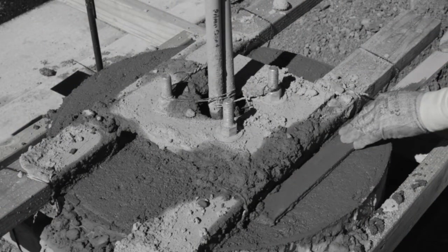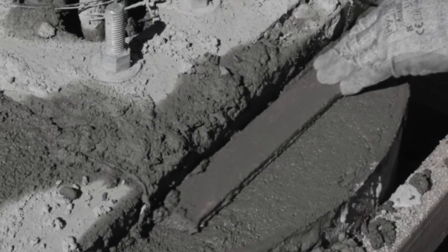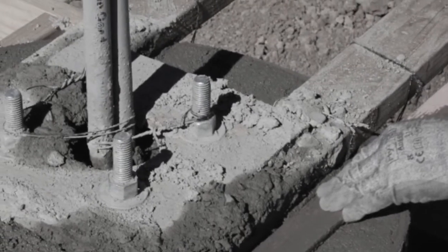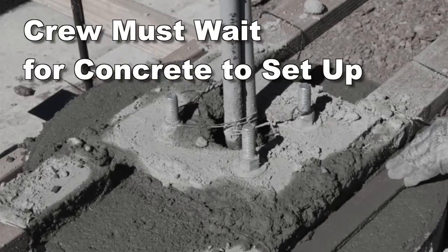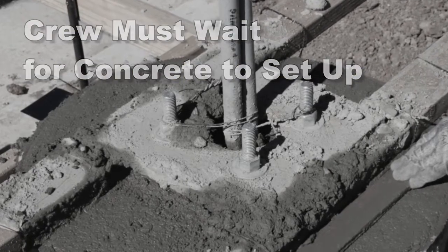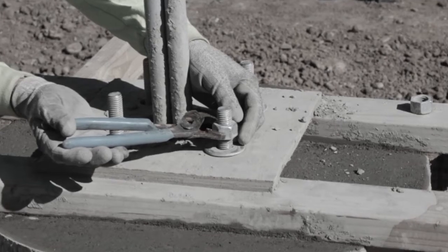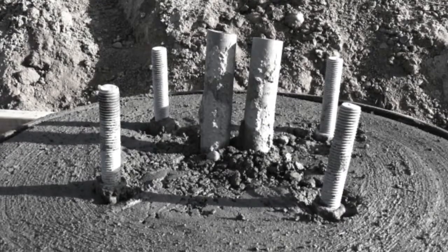But a huge inefficiency exists at this point with the conventional method. There's insufficient room to finish the entire pole base top in one step — the conventionally built pole templates get in the way. The crew must wait around for 30 to 45 minutes until the concrete sets up, and only then can the wood template be removed to allow performing the final finish. Pull the template too early and you run the risk of the bolt sinking or shifting.